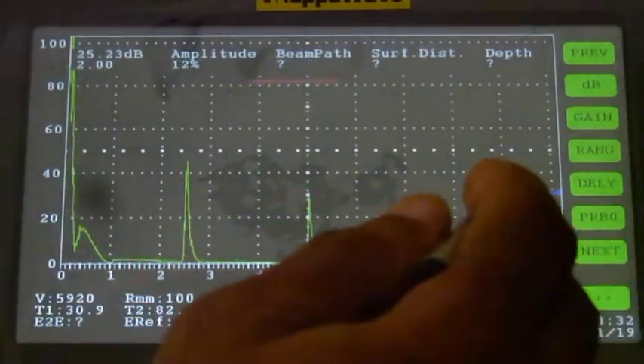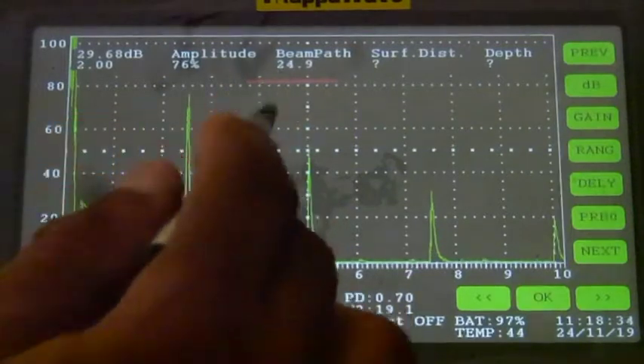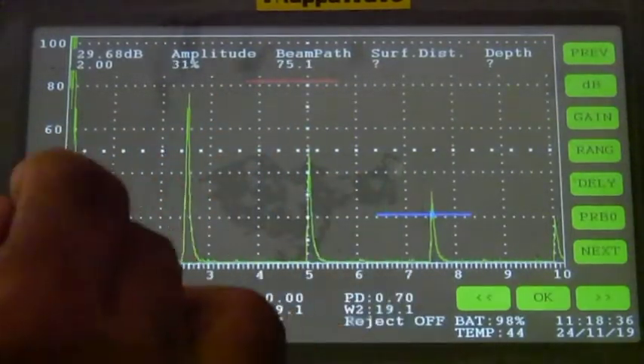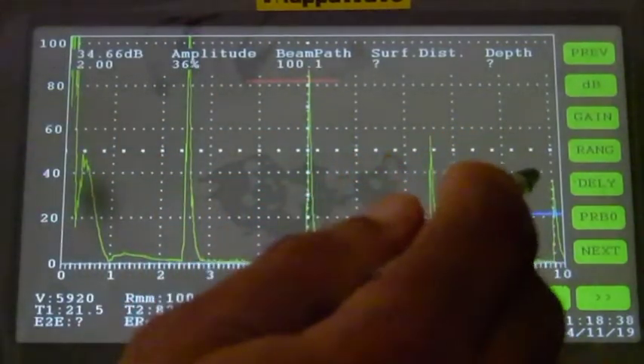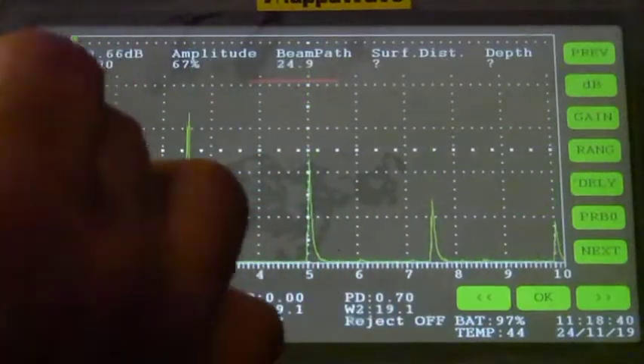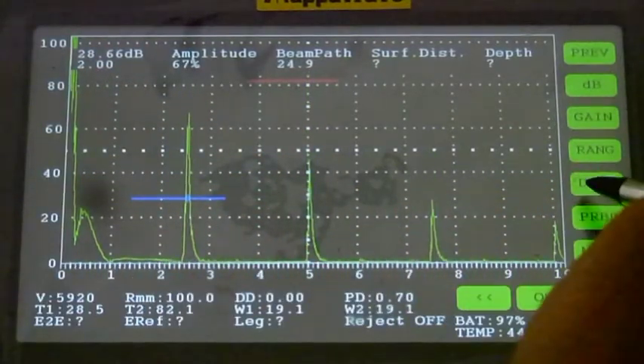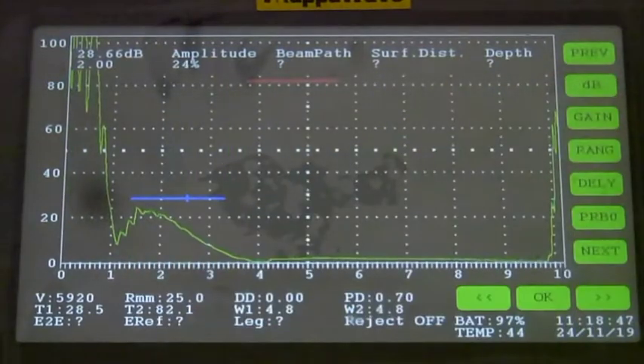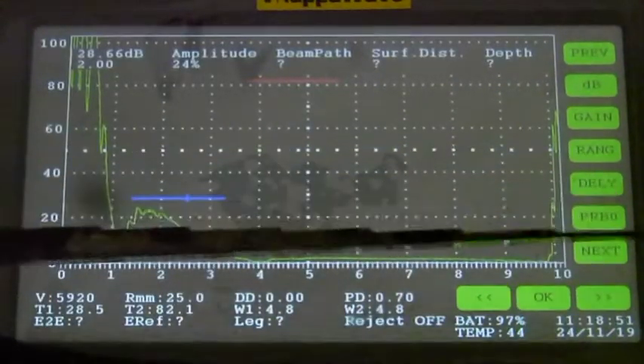Now the range may be changed to anything. For example, in this case 100 millimeter. And each of these thicknesses, like 25, 50, 75 and 100, can be verified. We are changing back to the 25 millimeter range now. Now this range may be used to measure thickness on this block.